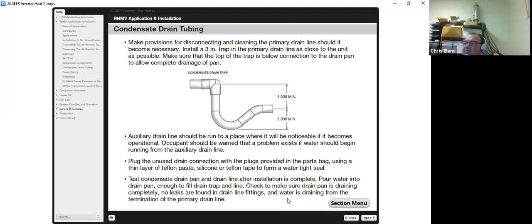The way I always did it, pour water in the pan, prime my trap. As I'm testing it, I can go back in any time during the test startup and actually watch water flowing freely from my drain. There's nothing more costly than a backed up drain, unfortunately.